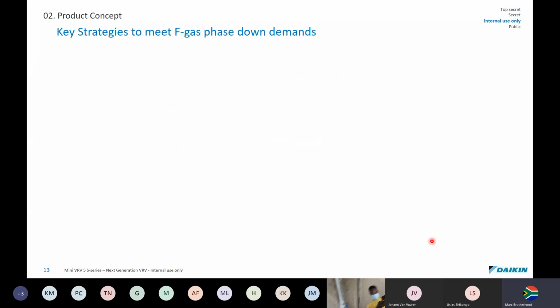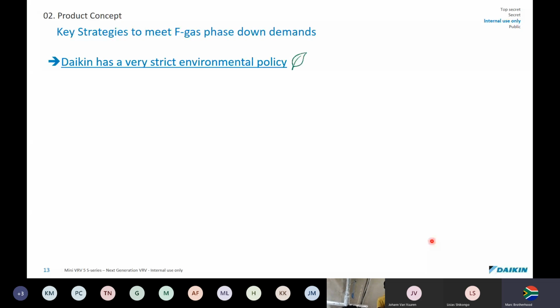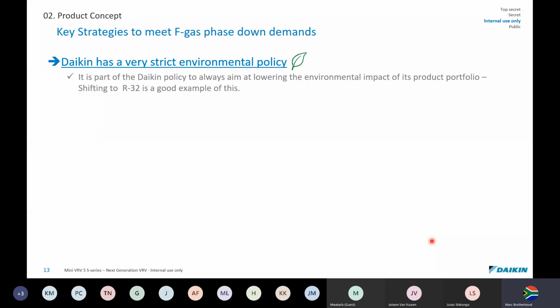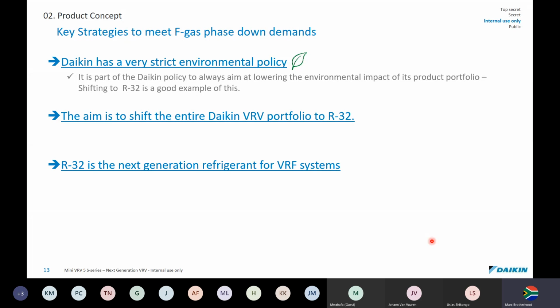So, the key strategies to meeting the F-gas phase down demands. Daikin obviously has a very strict environmental policy. It's part of the Daikin policy to always aim at lowering the environmental impact of its product portfolio. So shifting to R32 is a good example. The aim, which I mentioned earlier on, is to shift the entire Daikin VRV portfolio to R32 refrigerant. And R32 is definitely the next generation refrigerant for VRV systems. Why? It has a third the global warming potential of 410A.